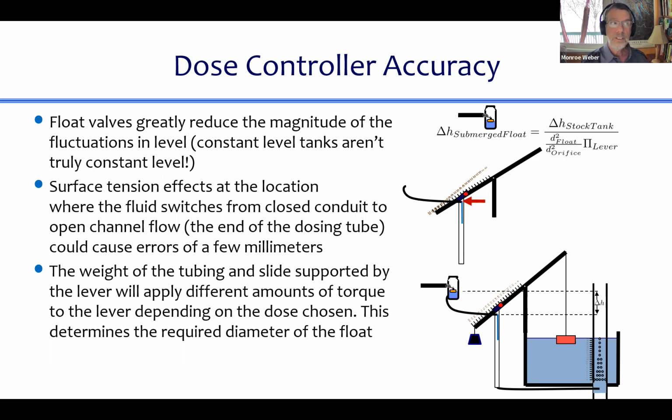So bigger float is better. And the only thing that prevents us from going really large is actually economics. A bigger float is better. Yay. So now if you go to the field and have to work with one of these, you will not trim the float to try to make it work better, because that never helps. Making the float smaller never makes it work any better. It only makes it worse.